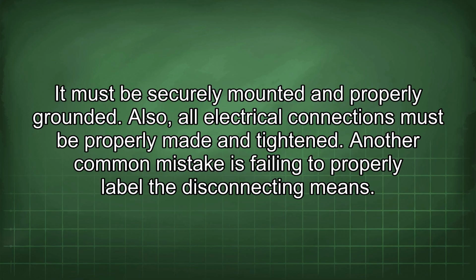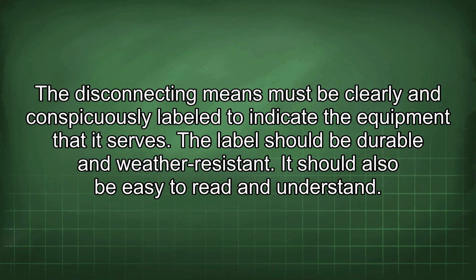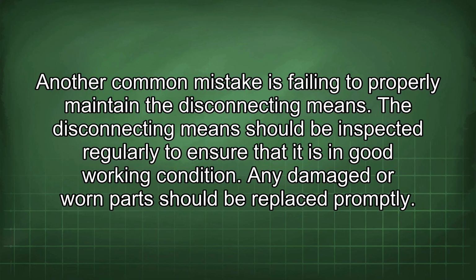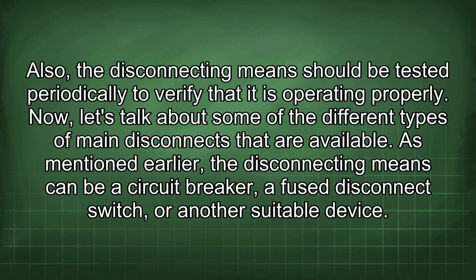Another common mistake is failing to properly label the disconnecting means. The disconnecting means must be clearly and conspicuously labeled to indicate the equipment that it serves. The label should be durable and weather resistant. It should also be easy to read and understand. Another common mistake is failing to properly maintain the disconnecting means. The disconnecting means should be inspected regularly to ensure that it is in good working condition. Any damaged or worn parts should be replaced promptly. Also, the disconnecting means should be tested periodically to verify that it is operating properly.